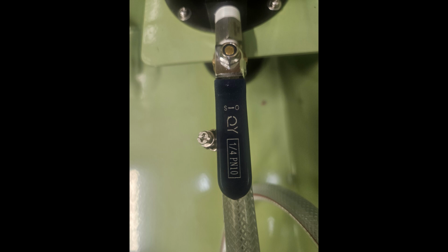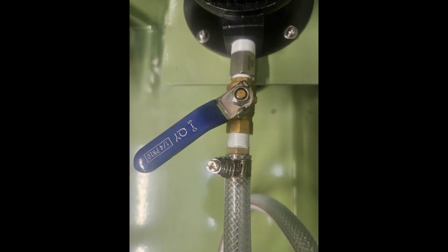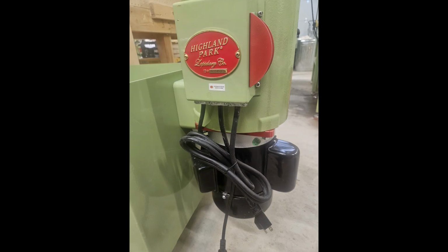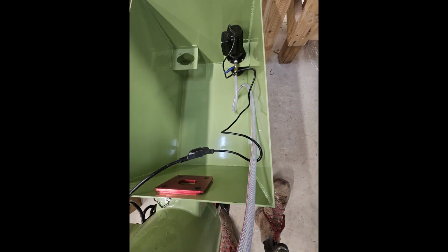I use the full length of my hose because I can remove the lid of the centrifuge, turn the pump on, and pump the clean oil back into the equipment that I've been working on. If you find that the pump motor on the outside of the tank is leaking or dripping oil, you close this valve down to reduce the circulation into the centrifuge. Here you can see that the valve is closed about 1/3 of the way. Next, you will notice a bundle of wires coming out of the switch box. There is a pigtail cord that plugs into the pump inside the tank.